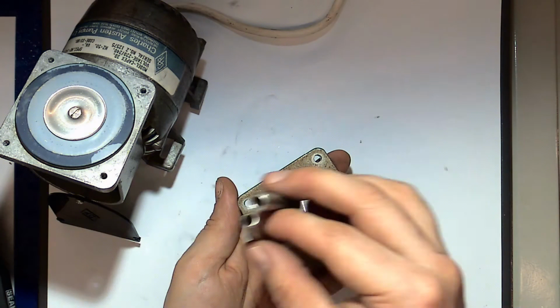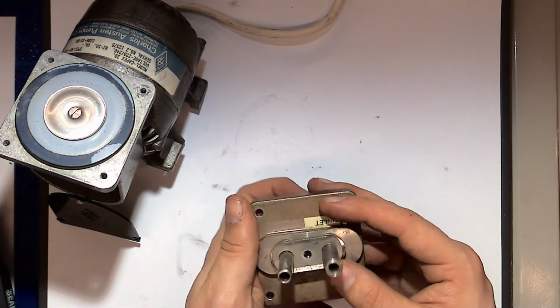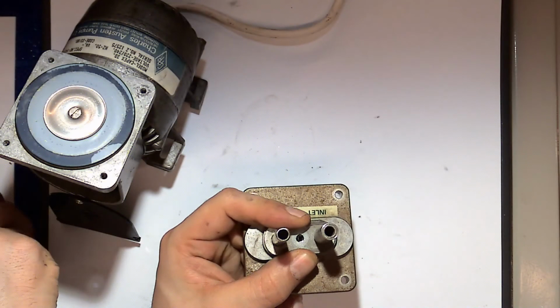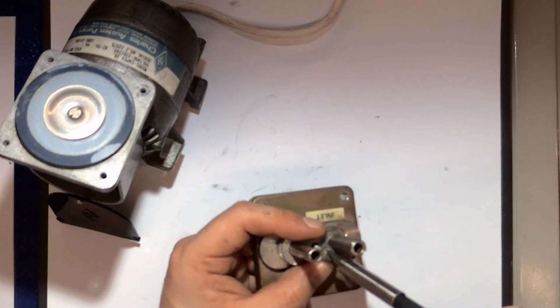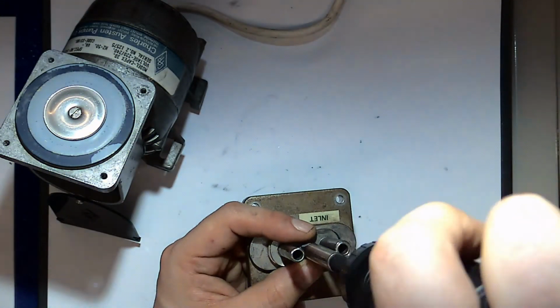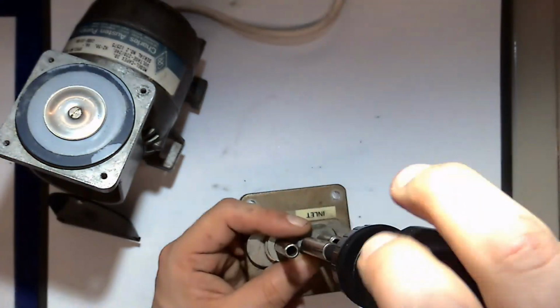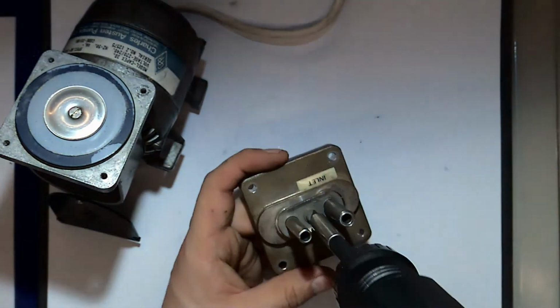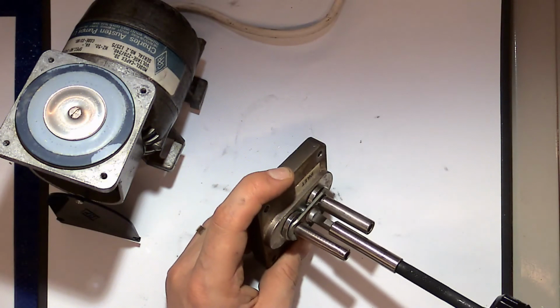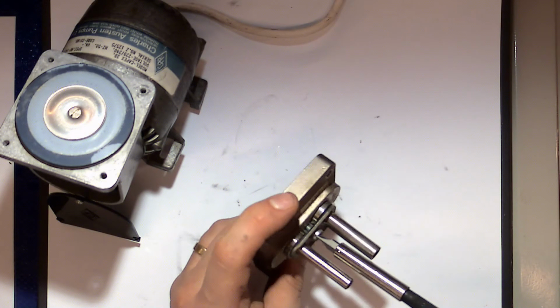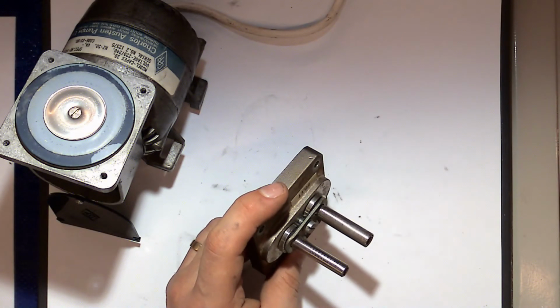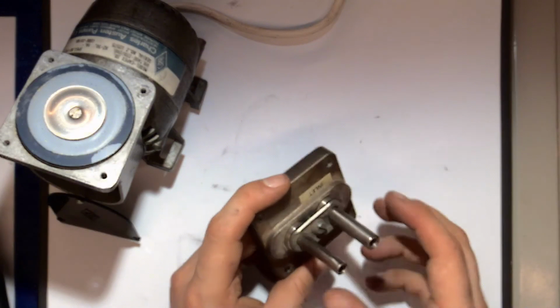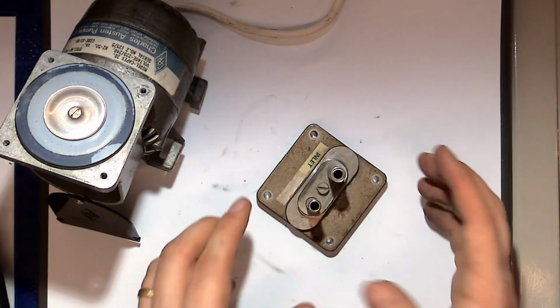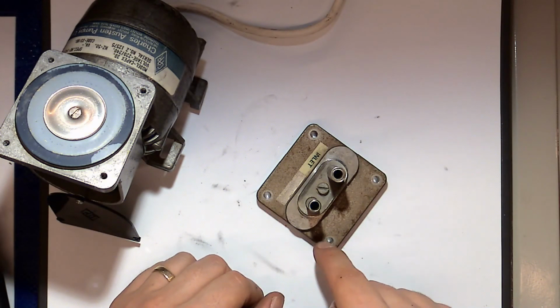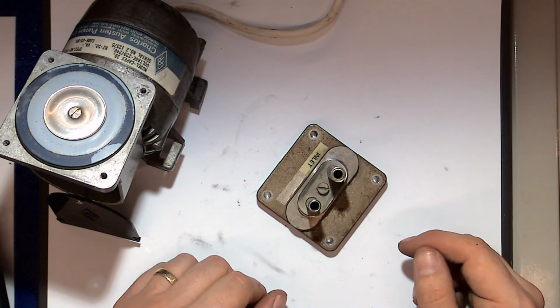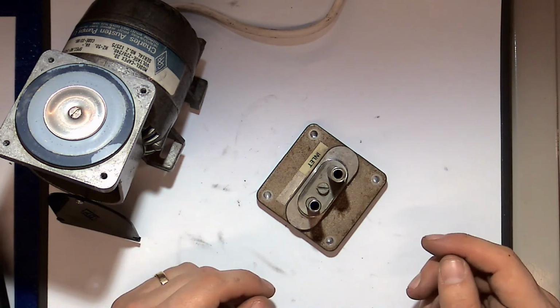Okay, and then reassembly, making sure everything's seated properly. Torque down as evenly as you can. Again, when you're designing, think about how it's going to go together. A single screw in the center is an excellent way of ensuring even torque, but if there's a lot of pressure required, if faces are mating rather than using O-rings, then you may struggle to do that. So instead you'll have to either have fully threaded components, or you cross tighten your screws as you go. Okay, so that's how this particular diaphragm pump works.